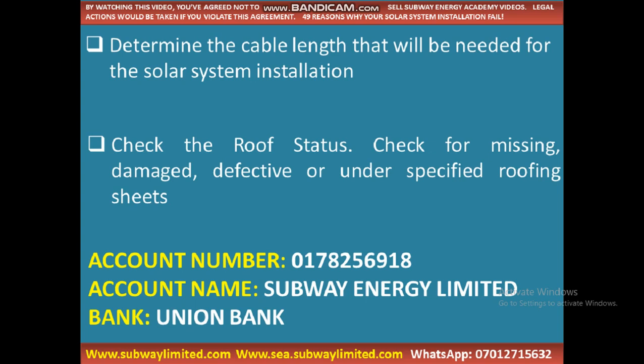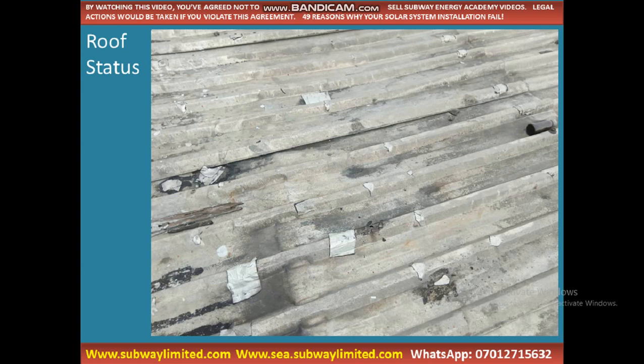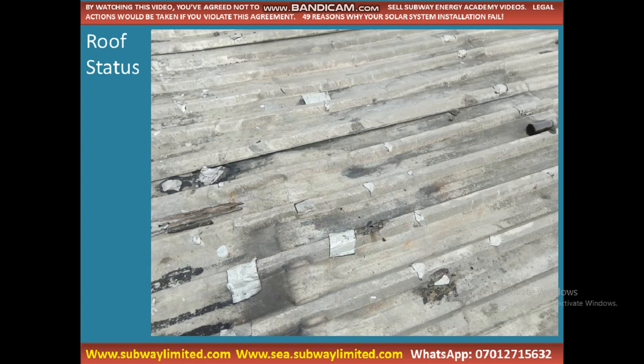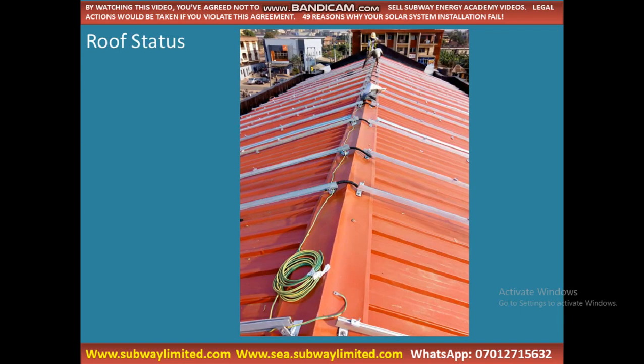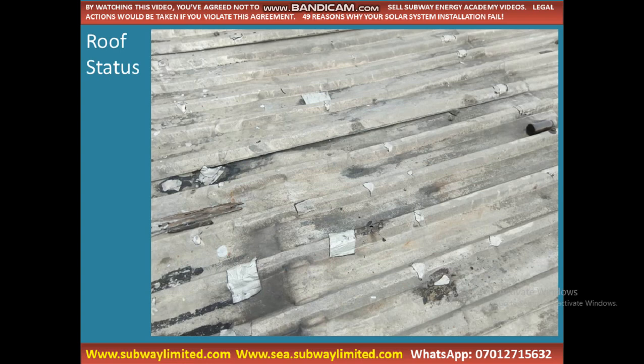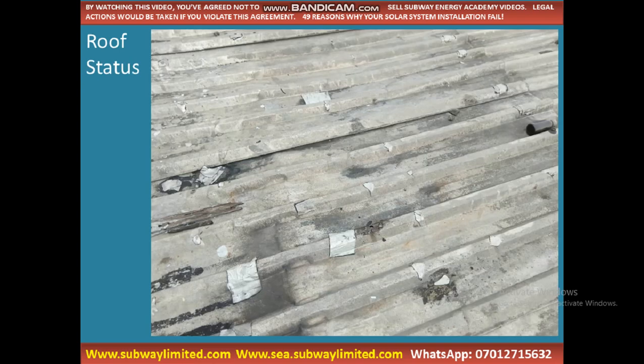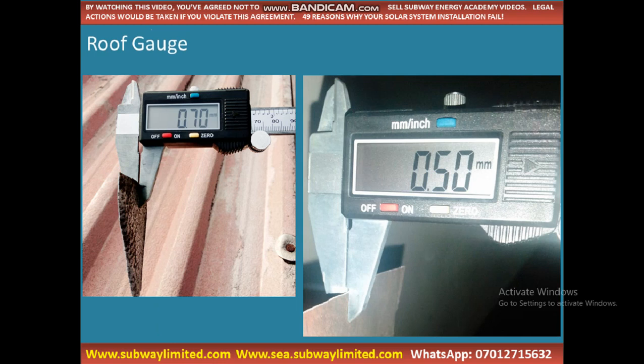We'll talk about roof status now. If you go for a power audit and you encounter a roof in poor condition like this, please advise the client — it is a must to work on the roof to bring it to proper standard. If you complete the installation on a bad roof, there will be serious leakage after mounting the solar panels and the client will not be happy. Always check the roof status and always check the roof gauge using the caliper.